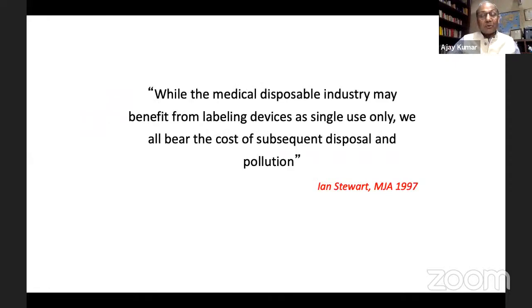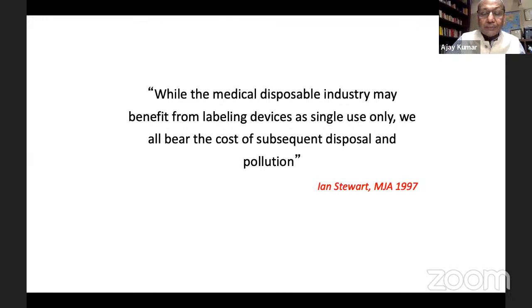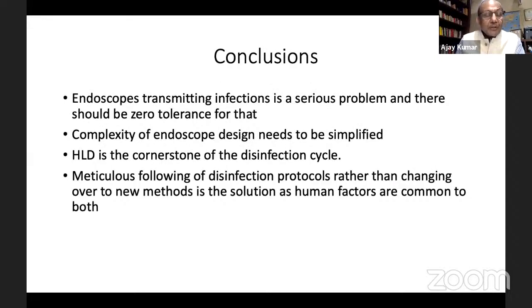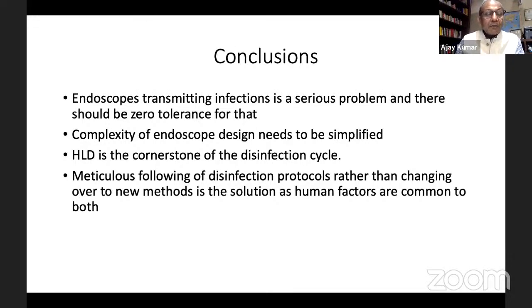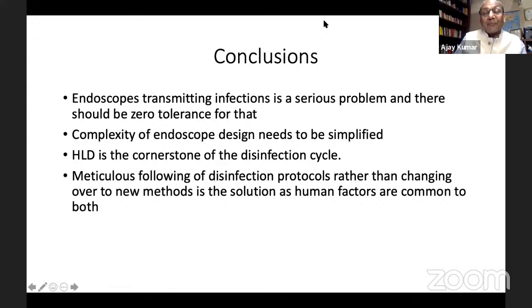Disposable endoscopes are available, with two models already on the market and good studies available. But the key question remains: can we afford it, and what about the medical waste they produce? As a famous saying goes, while the medical disposal industry may benefit from labelling devices as single use only, we all bear the cost of subsequent disposal and pollution. In conclusion, endoscope-transmitted infections are a serious problem with zero tolerance required, but we need to simplify endoscopic designs. High-level disinfection is the cornerstone of the disinfection cycle, but following protocols matters more than changing methods, since human factors are common to both.